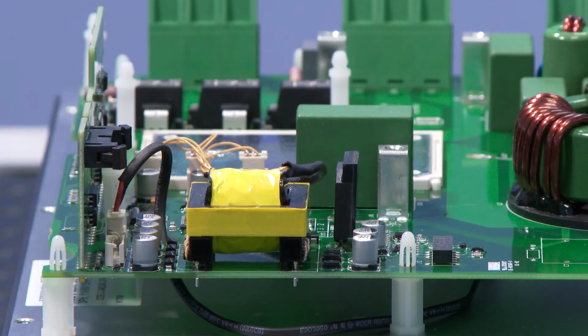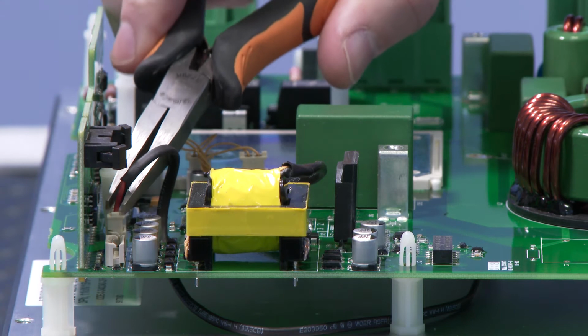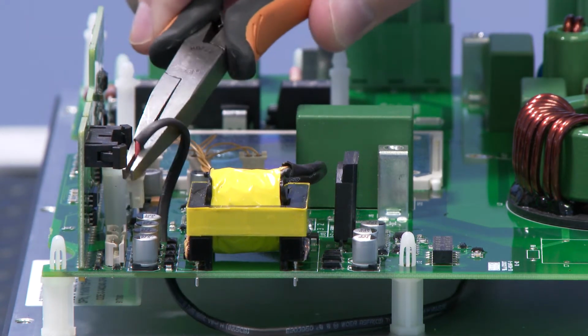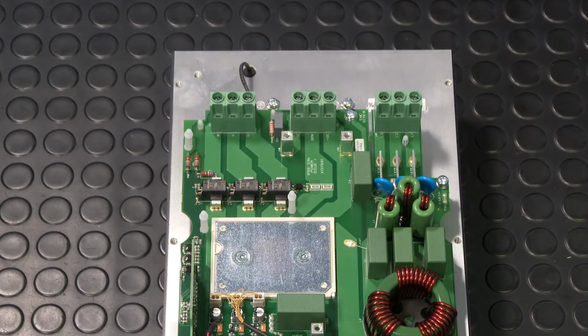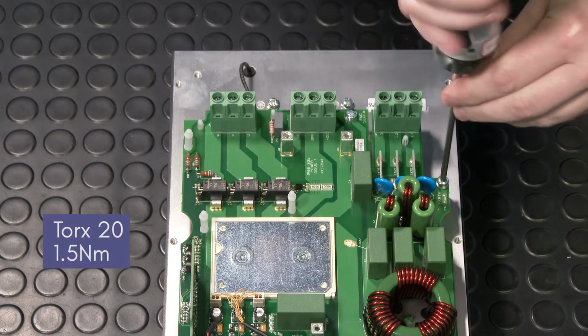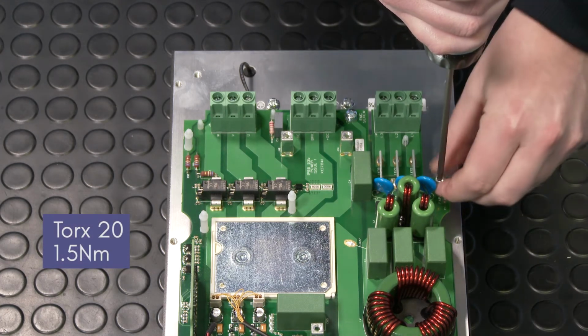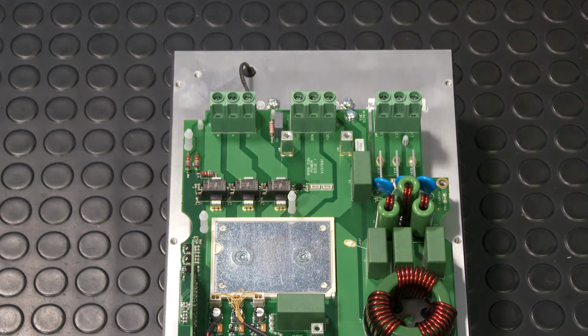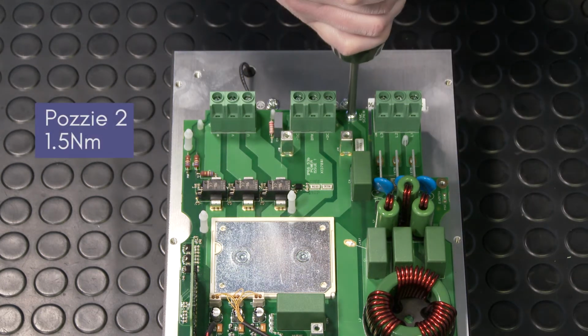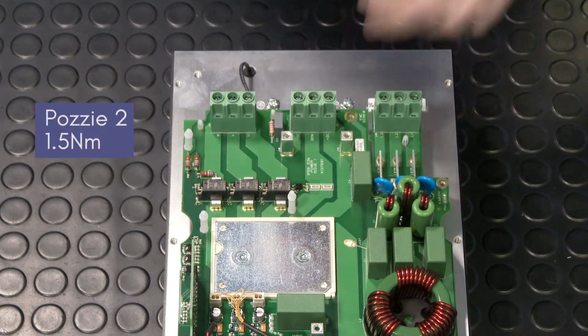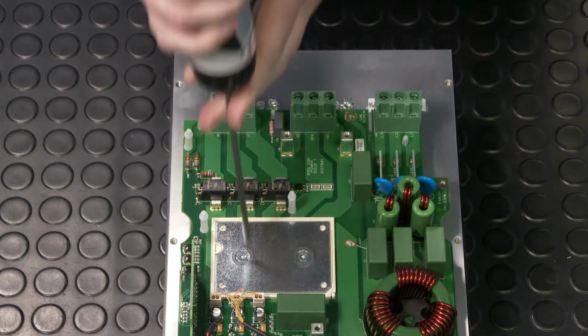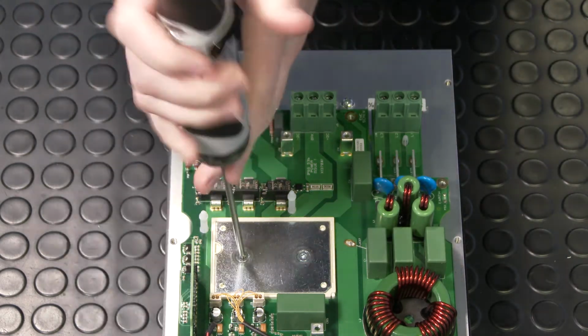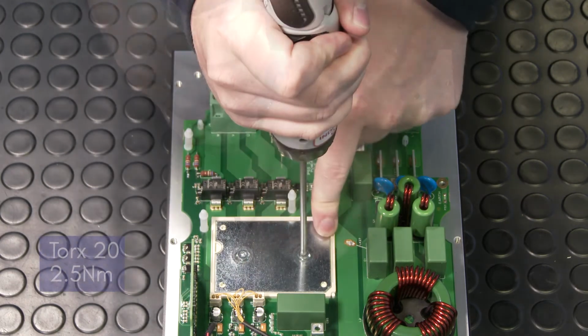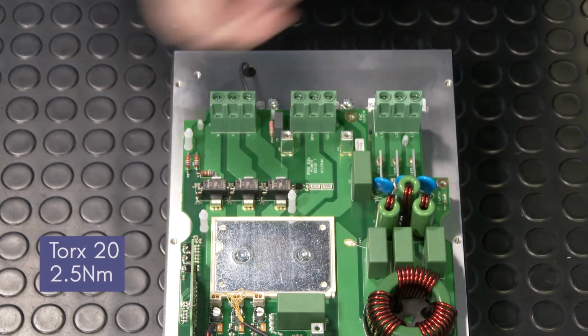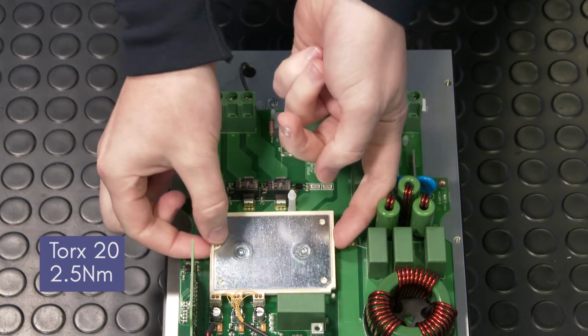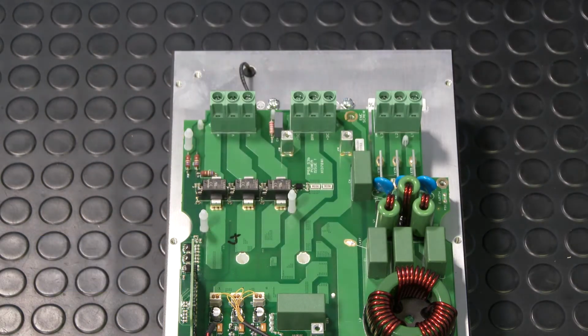If your drive does have a heatsink cooling fan, remove it by using long nose pliers to disconnect the fan connector. Use a Torx 20 screwdriver to remove the earth screw. The torque setting is 1.5 Nm. Use a Posi 2 screwdriver to remove the EMC screw. The torque setting is 1.5 Nm. Use a Torx 20 screwdriver to remove the 2 power module top plate screws and lift the top plate away. The torque setting is 2.5 Nm.